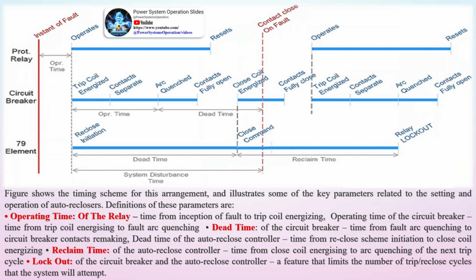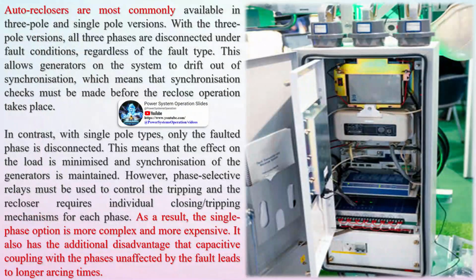Delayed auto-reclosing: in this case, no problems are there related to fault arc deionization time, CB operating characteristics and power swings on the system decay before closing. All tripping and closing shall be 3-phase only. In addition, the practice of checking system parameters before closing.